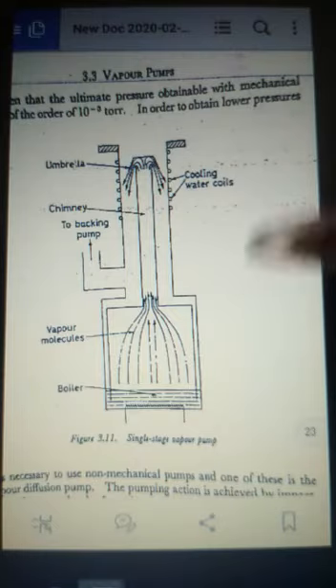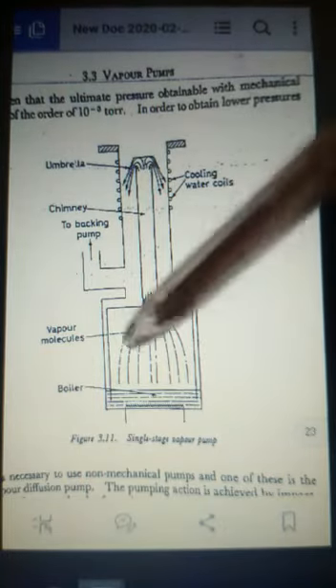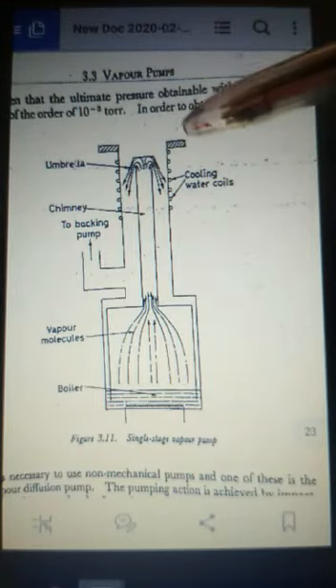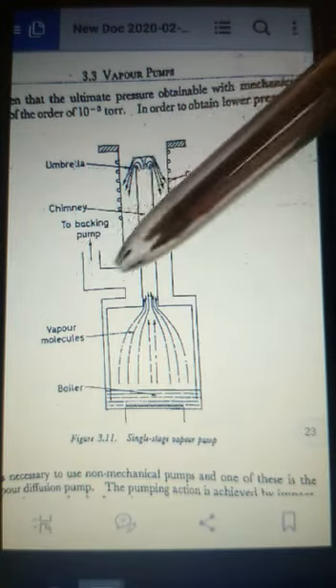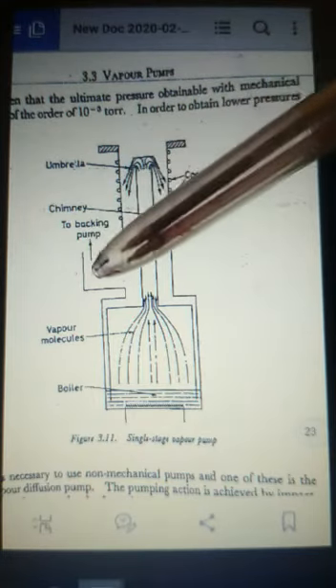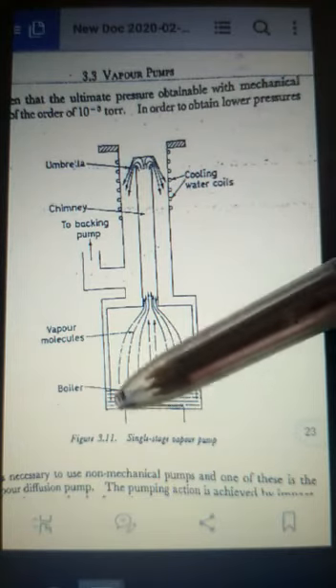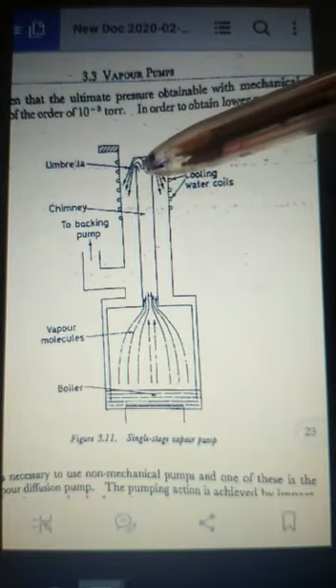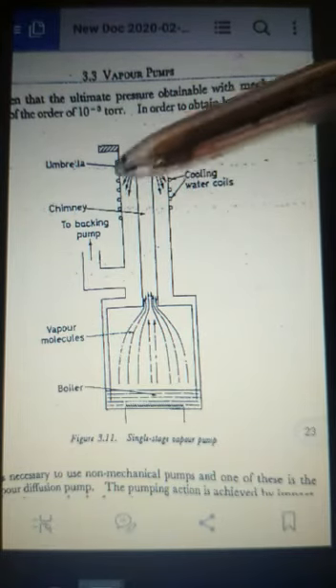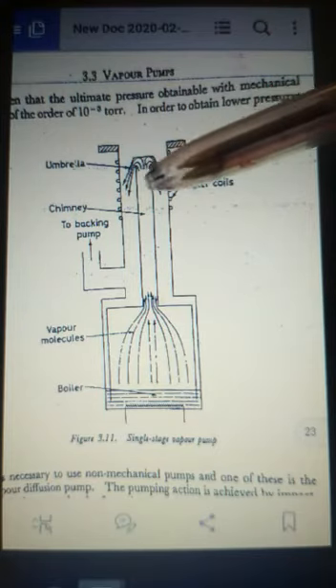One of these is the vapor diffusion pump. The pumping action is achieved by imparting the gas molecules from the system a momentum in the direction downward to the exhaust. This is the exhaust backing pump. Here we boil the oil and this vapor goes up.